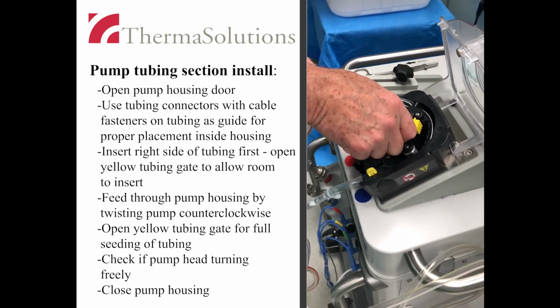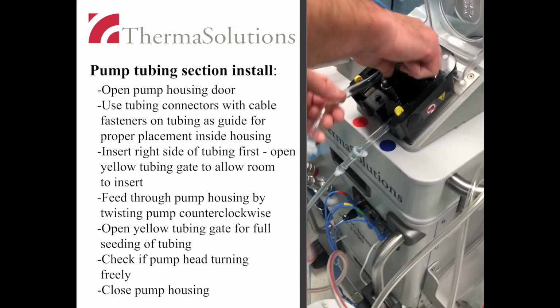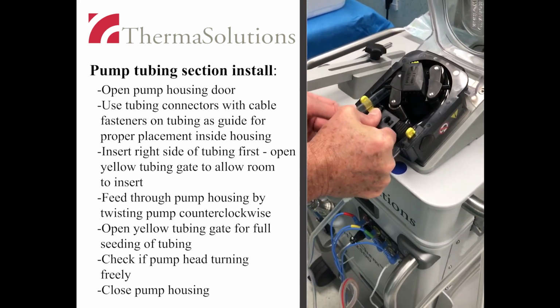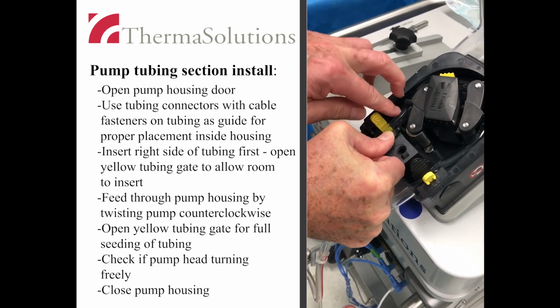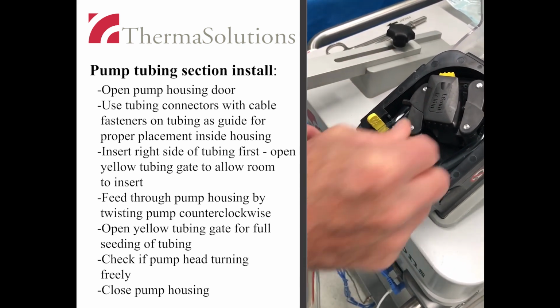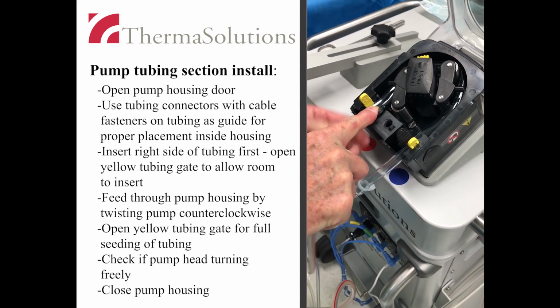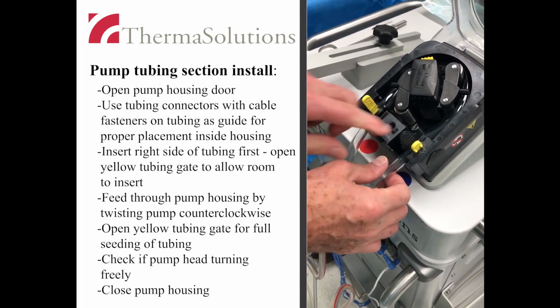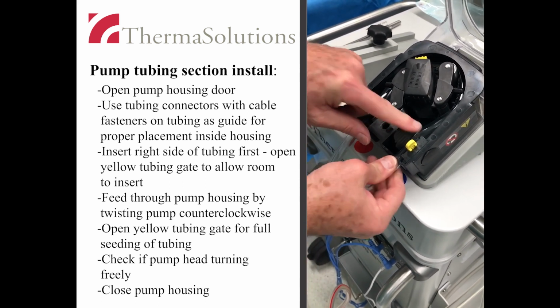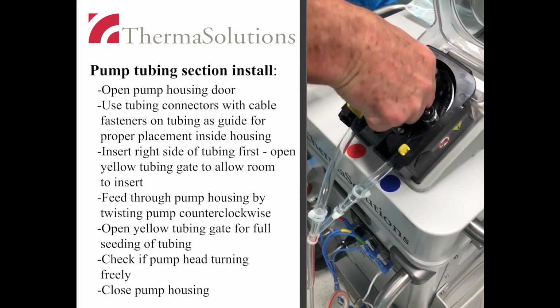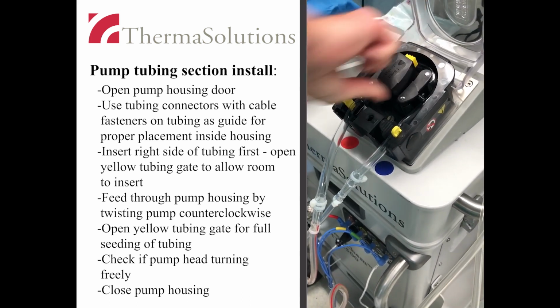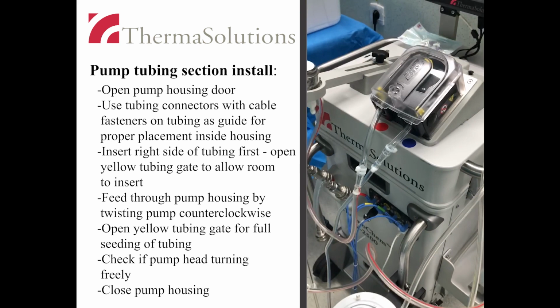Insert the right side of the tubing first by opening the yellow tubing gate to allow room to insert the tubing. Feed the tubing through the pump raceway by turning the pump counterclockwise. Open the yellow tubing gate on the left side to allow for the other end of the tubing to insert. Check if the pump head turns freely. Close the pump housing door.